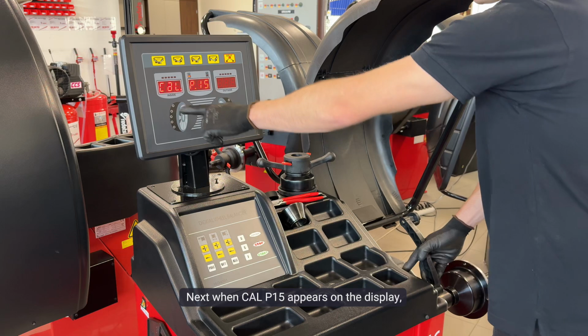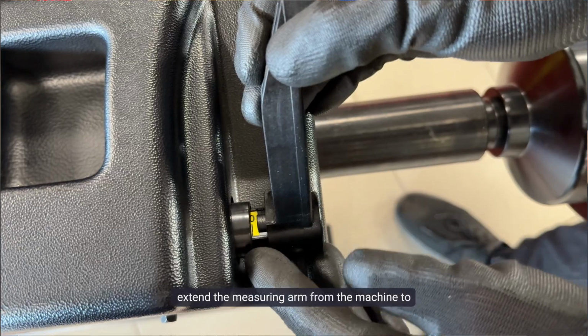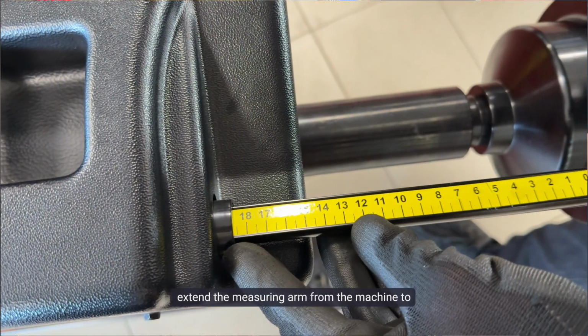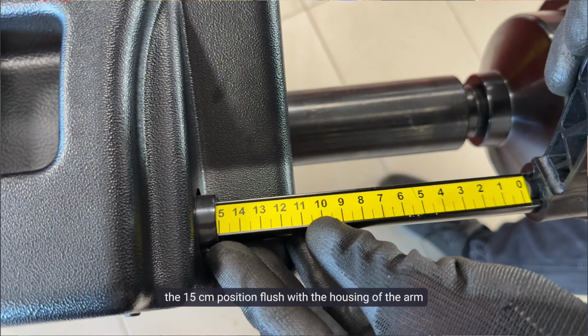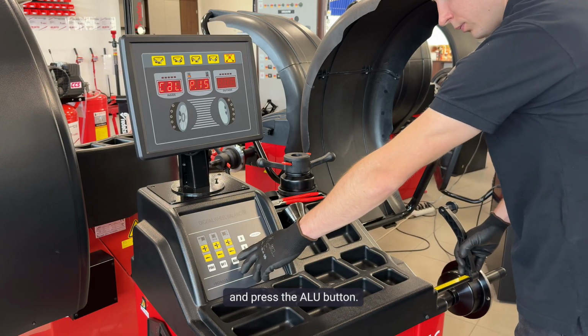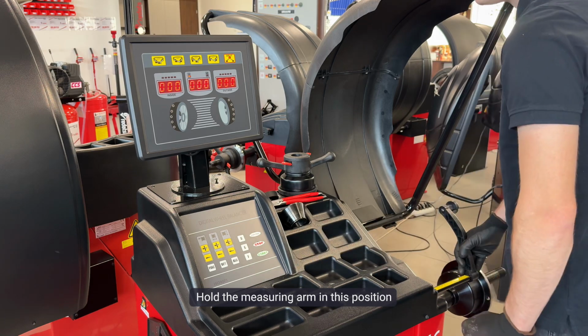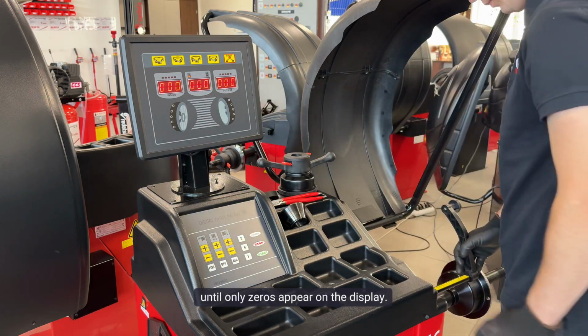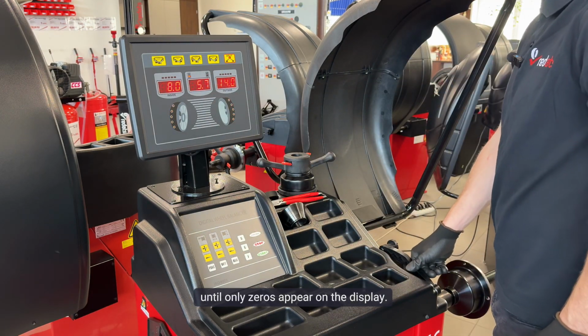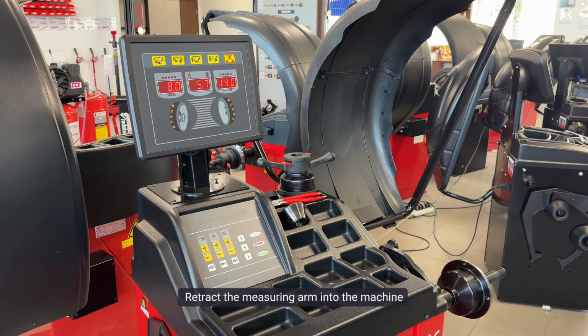Next, when Cal P15 appears on the display, extend the measuring arm from the machine to the 15 cm position flush with the housing of the arm and press the ALU button. Hold the measuring arm in this position until only zeros appear on the display. Retract the measuring arm into the machine and this calibration is complete.